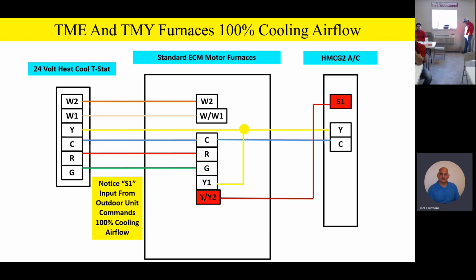So the outdoor unit, as you can see, is very, very simple 3-wire, in this case, 24-volt wiring. But what the outdoor unit is doing is constantly monitoring the suction line temperature, liquid line temperature, and hot gas line temperature, so it knows what the capacity on the refrigeration circuit is. It's also comparing that to outdoor ambient temperature and thermostat activity. It's all proprietary engineering, the algorithms inside that board.